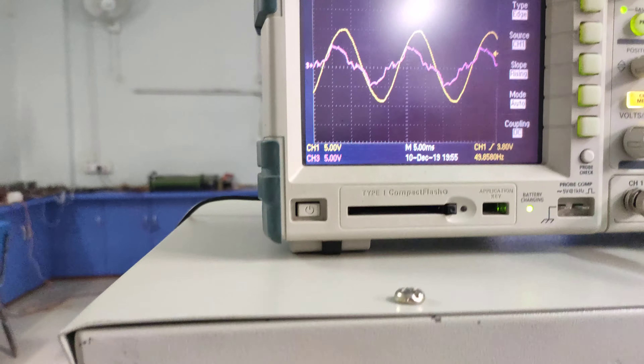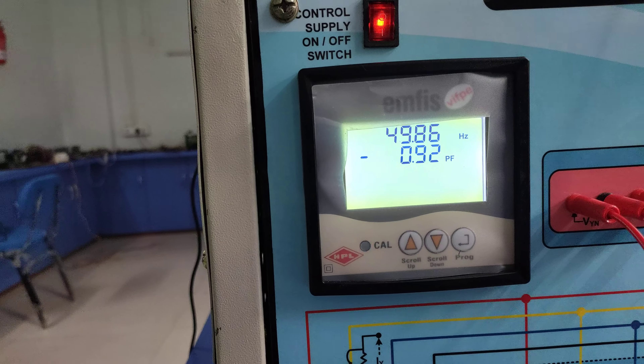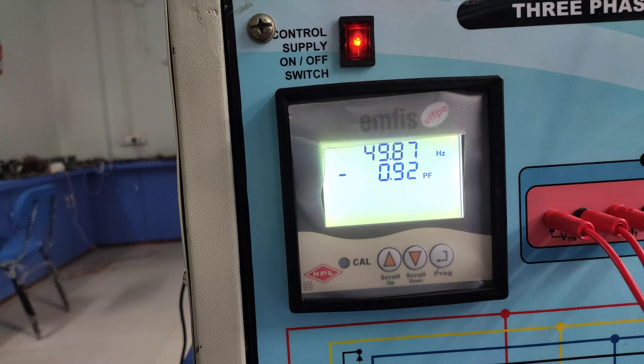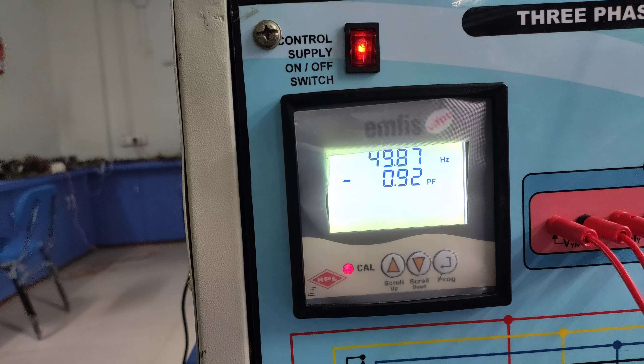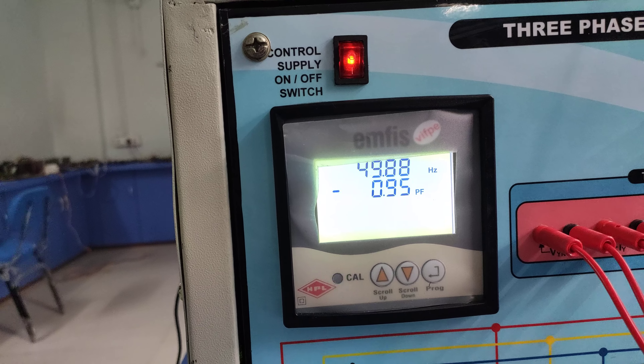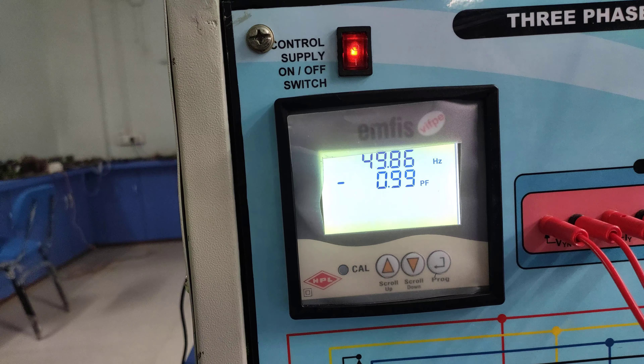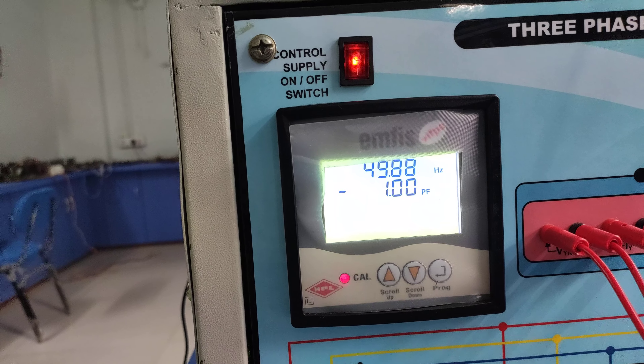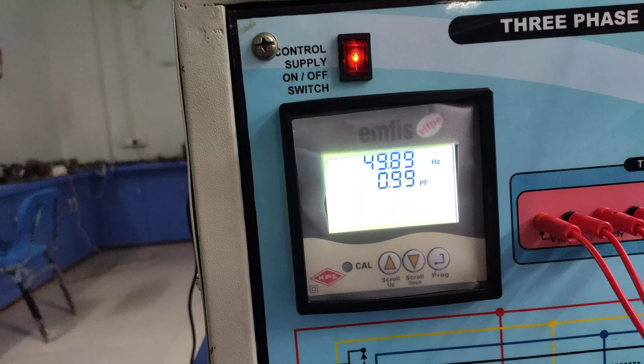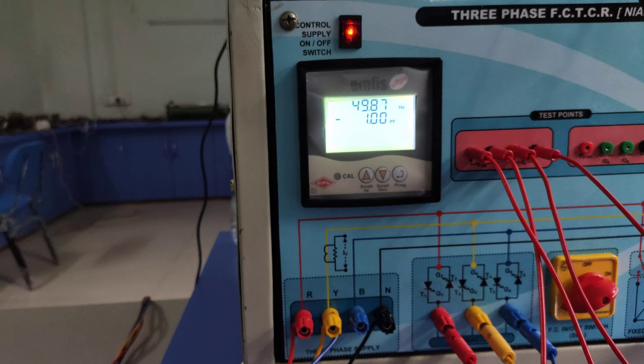I just turn off my third switch — again the current will be leading and the power factor is poor at 0.92 or 0.93. The controller will take action to make the power factor unity. It will take around 2 to 3 seconds for the action to complete, and again your power factor will be unity.